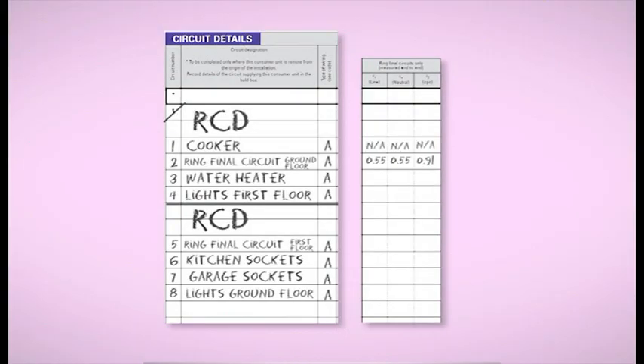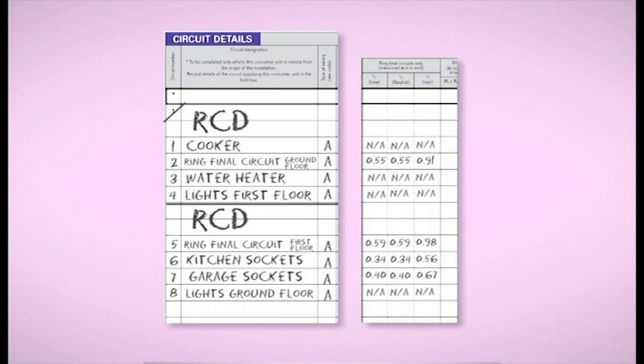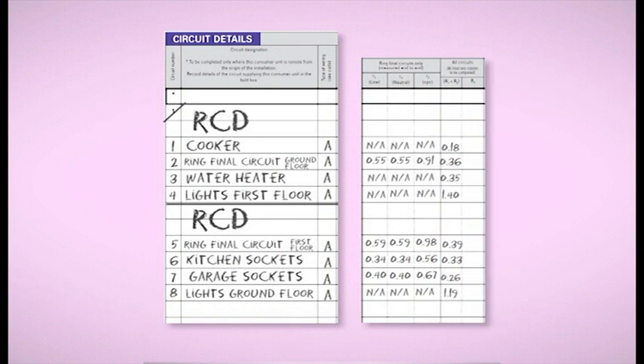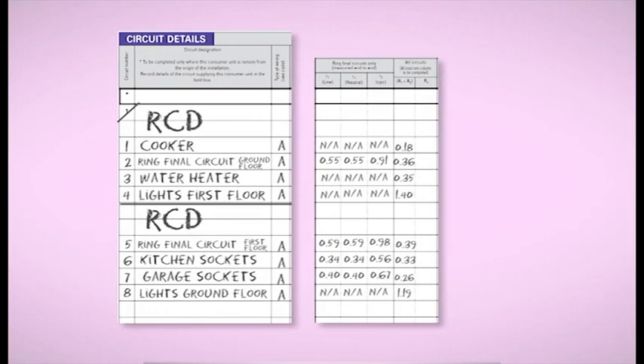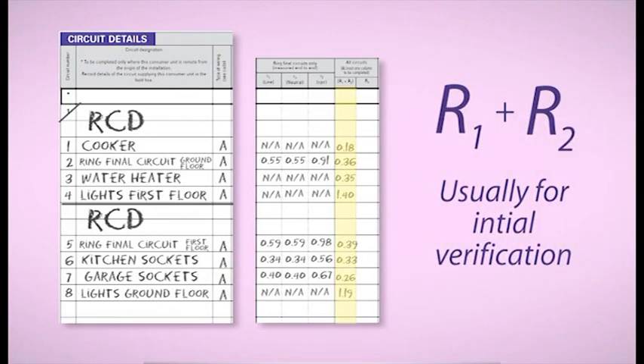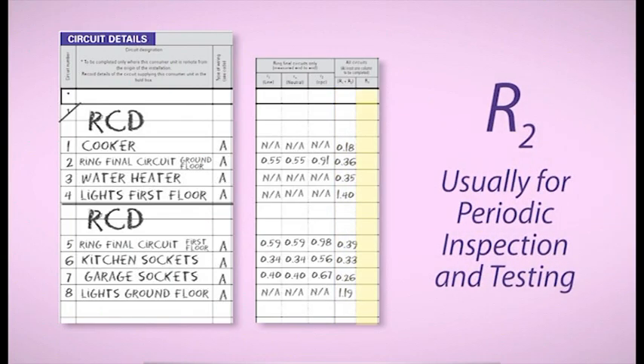The first three columns are for little r readings for ring final circuits only, and not applicable can be recorded for all other circuits. Next we have two columns for big R readings for all circuits, but only one column need be completed for each circuit. For initial verification, it is good practice to do the R1 plus R2 option. The R2 test is usually undertaken on periodic inspections as a convenient method of determining that a CPC has been provided at every accessory and outlet.